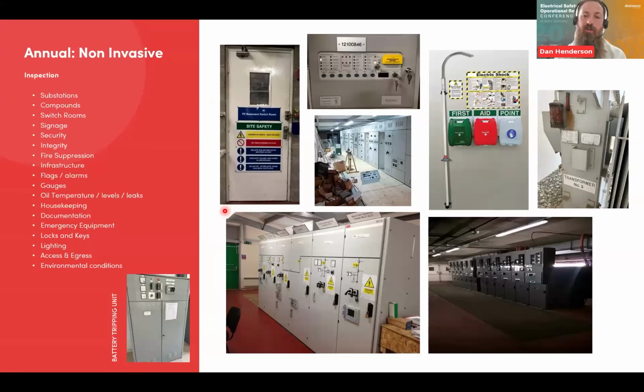So then we're going to start looking at the system itself. So we're going to be looking at things like the switchgear, the transformers. We're going to be looking for any flags or alarms on the relays or any other protection systems we might have. Gauges. So if we've got any gauges for oil levels or SF6 levels, to make sure they're in the right location.